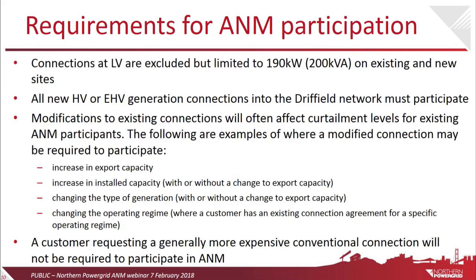Moving on to some of the requirements for ANM participation at Driffield. Basically, all new customers greater than 190 kilowatts, it's around 200 kVA at a 0.95 power factor, will have to either join the ANM scheme or contribute towards reinforcement costs. This effectively means that all HV and EHV generation must join the ANM scheme or contribute towards the reinforcement that will be necessary to get them connected. Some of the reasons why existing connections might affect curtailment levels for existing ANM customers are changes to capacities within the bounds of the first point on the slide, changes to generation types and operating regime changes.